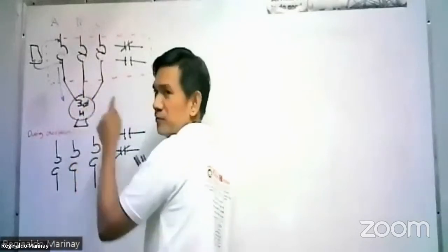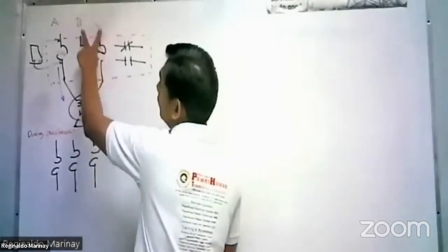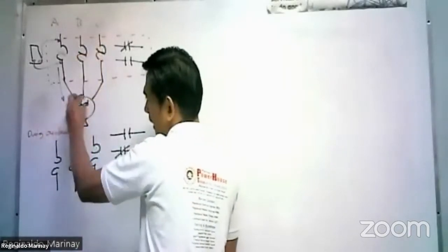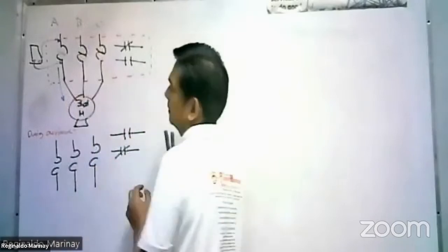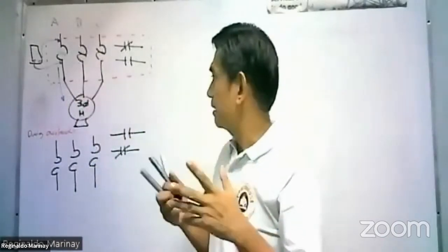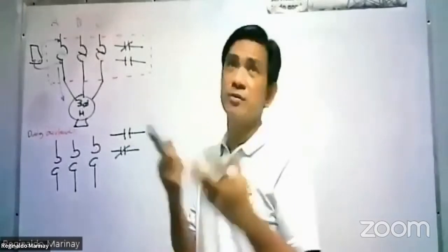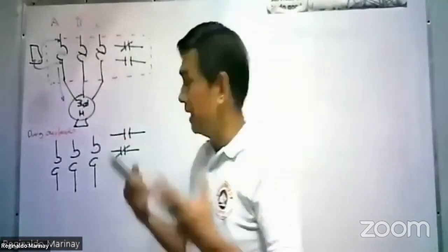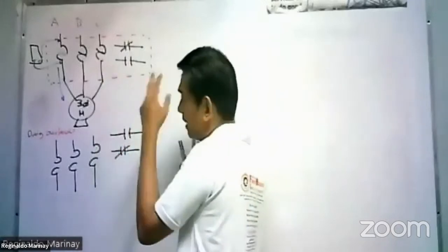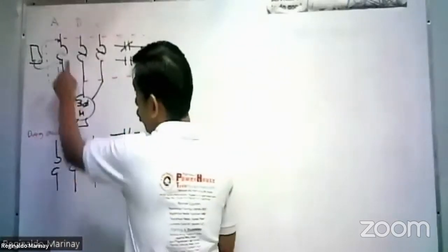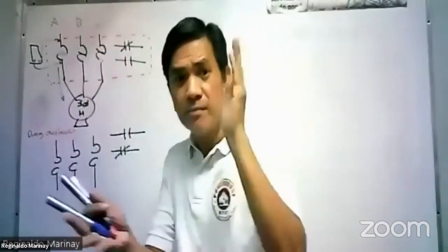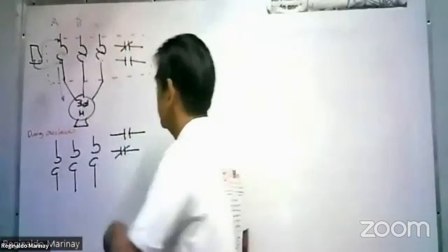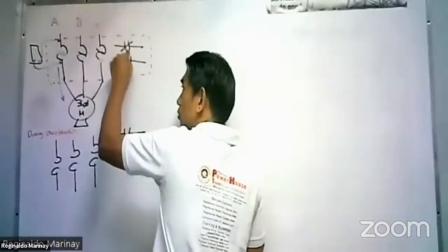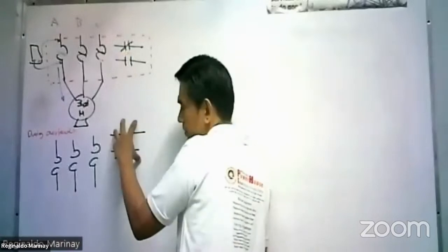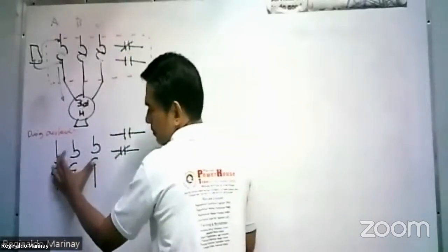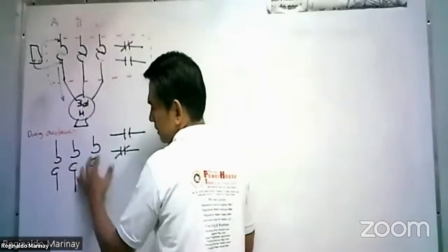But your motor is a three-phase motor. A large amount of current would flow to B and C, and this will become overloaded. That will heat up and may burn the windings. That's dangerous for our motor. That is why if there is an overload, all three contacts must open simultaneously. And then this normally closed will become open. This is on the part of the control circuit, and this is on the part of the motor circuit.